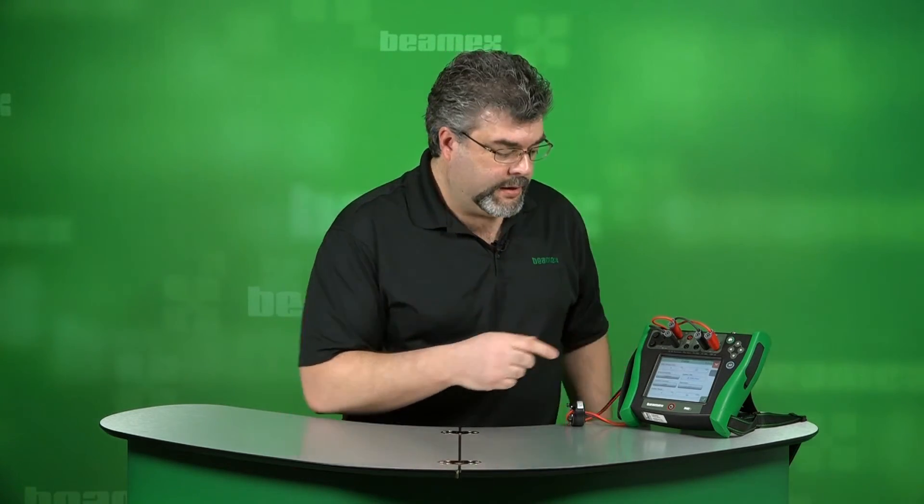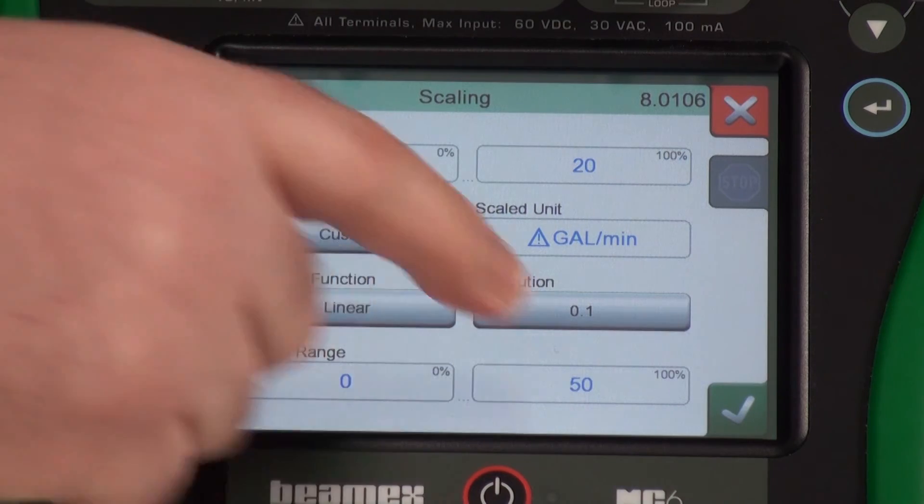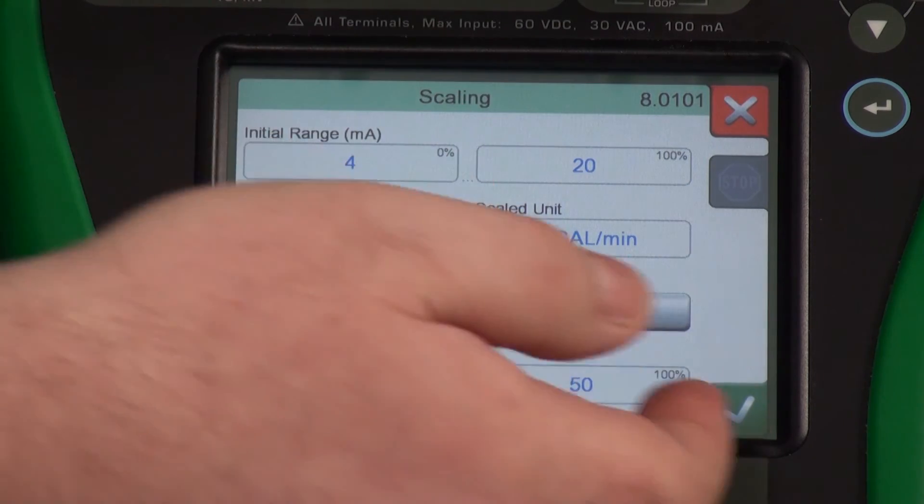Let's do something ridiculous. Let's convert our temperature input to what our DCS might be showing. So we have 0 to 100 input. And let's say that on a display in the control room, 0 to 100 degrees Celsius equals 0 to 50 gallons per minute. 4 to 20 equals 0 to 50 gallons per minute. And we'll just hit check.